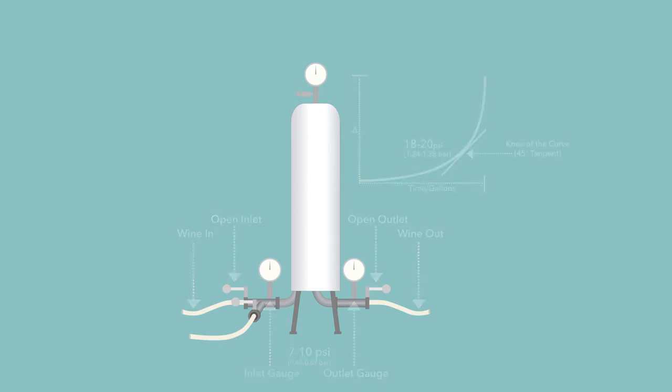Once filtration is complete, close product outlet valve. Pressure should be released slowly from the system and residual liquid drained. Post rinse of the filter can be achieved by introducing a forward flow of water, closing inlet and outlet valves, and opening inlet water valve and discharge valve.